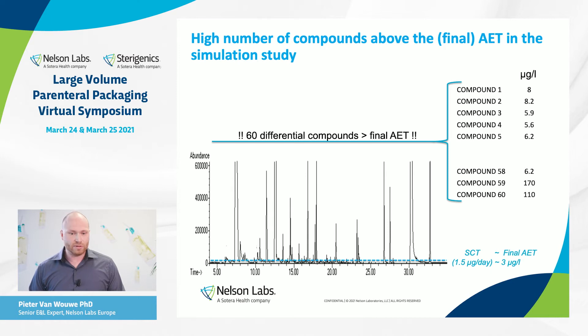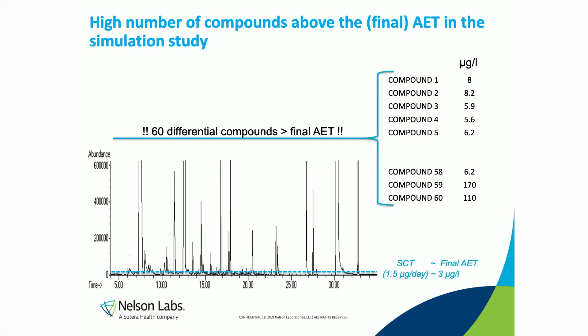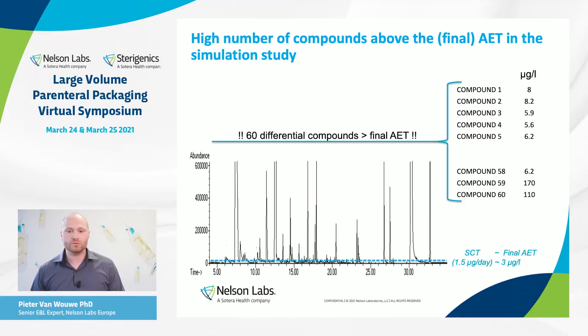Looking at a case study: this is a GC-MS chromatogram from a simulation study on a large-volume parenteral bag system, and we had 60 compounds present above the final AET level. If we need to monitor 60 compounds in a leachable study, that would be very hard from a practical point of view — it will cost a lot of time and would not be cost-effective for our customers. Therefore, we have an alternative approach.